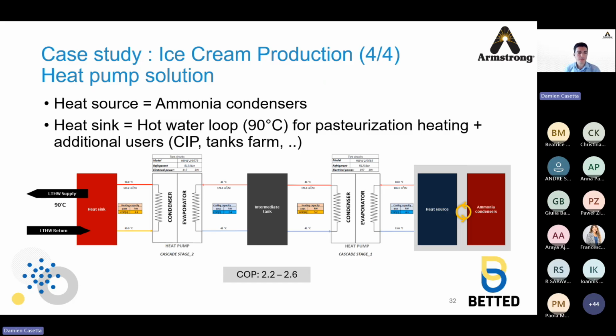Secondly, the heat pumps come into play. Here we have as a source the ammonia condenser. Remember, low temperature, large quantity of heat that in the Sankey we've just seen that was wasted. The heat pump is supporting in reusing that heat and bringing back to the system where heat is needed, here it's on the hot water loop at 90 degrees that is feeding both pasteurization and additional users such as CIP and tank farm.